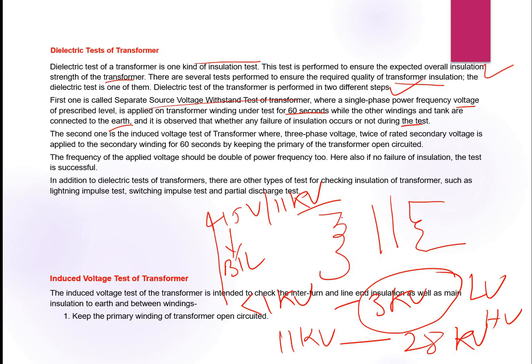Connection will be, if you apply on HV side, this is the HV and this is the LV. If you apply voltage on HV side, 11 kV side, short all the winding and apply separate 28 kV for 60 seconds, and other winding should be connected to the ground. Same thing on LV side, as per voltage level. So in this way, you can also test the separate source voltage withstand test of transformer, where a single phase is applied for 60 seconds.